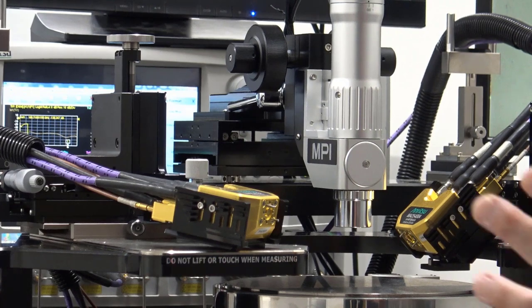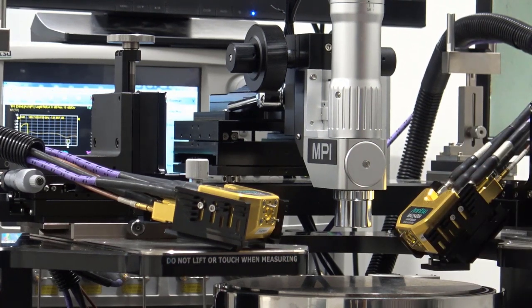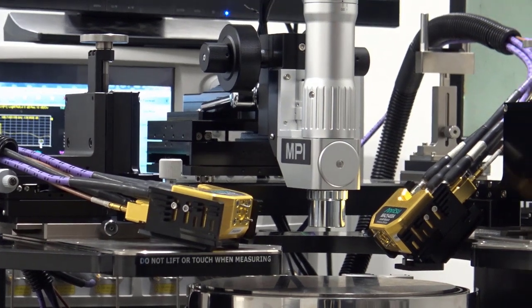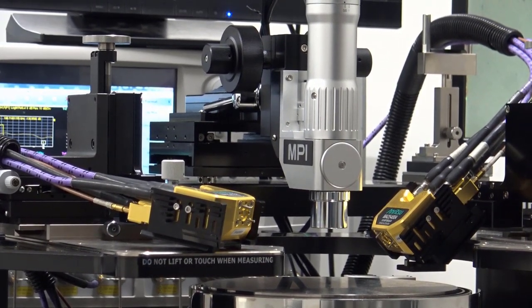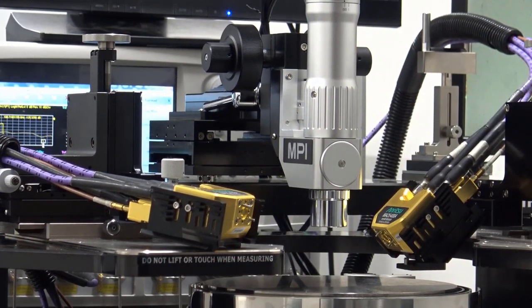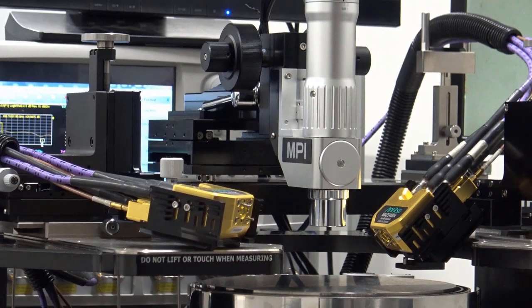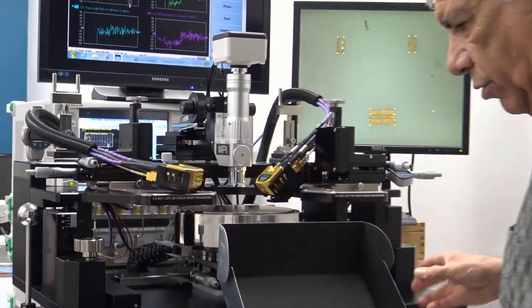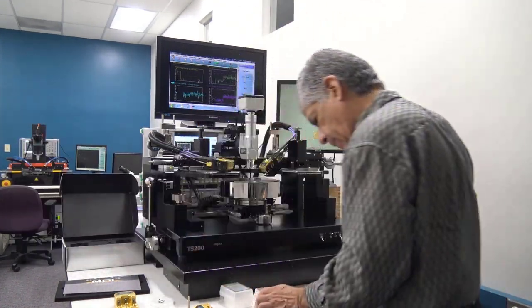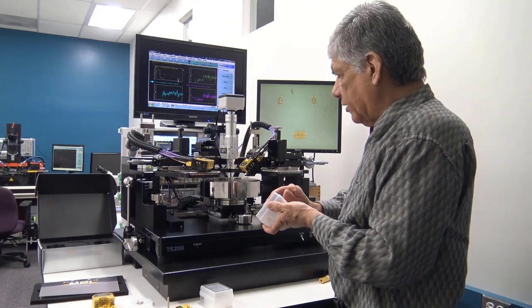And then we take our probes and mount in this position. So we'll get our probes out. And these are 75 micron pitch probes, the T220 from MPI.